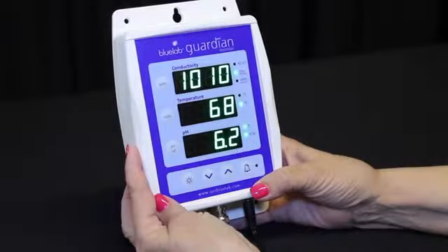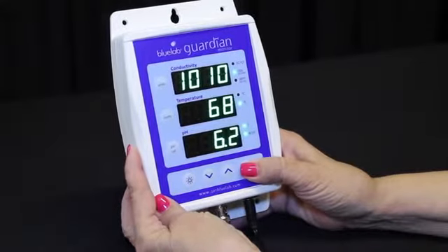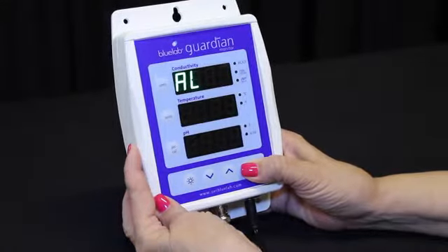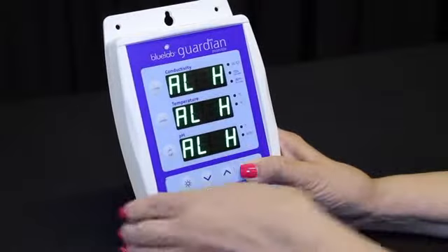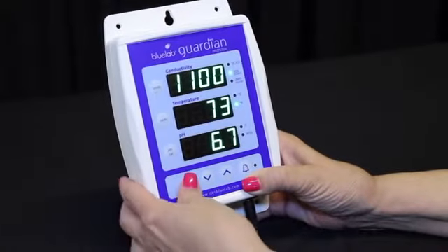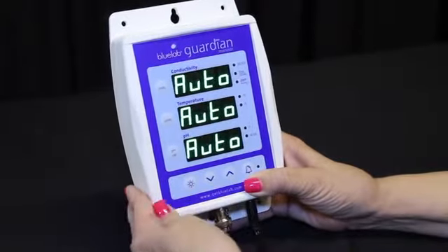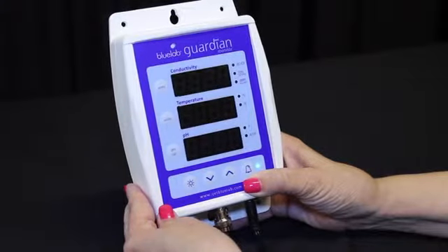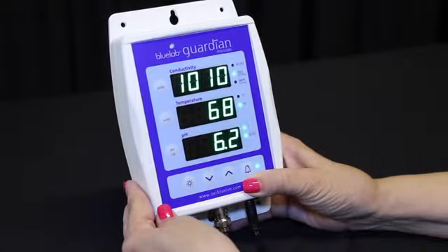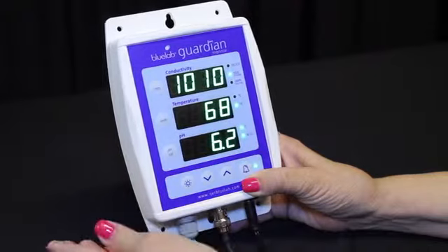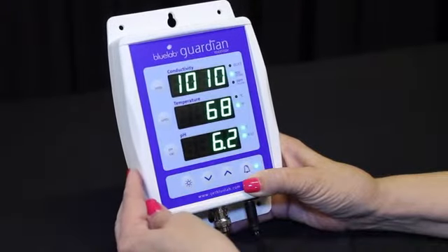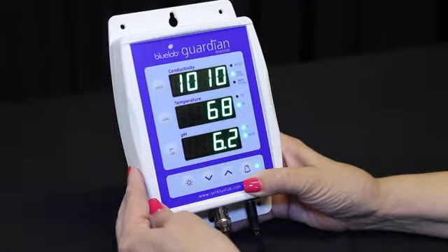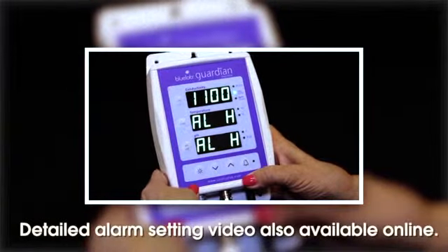To activate the quick set, press and hold the alarm button until ALH is displayed in all 3 windows. Release the button. Press the brightness button once. All 3 windows display auto for 1 second, then save will show in the conductivity window. The alarms are now automatically set and the alarm LED will glow indicating it is activated. If you wish to manually input high and low alarm settings, watch the Guardian Monitor alarm setting video.